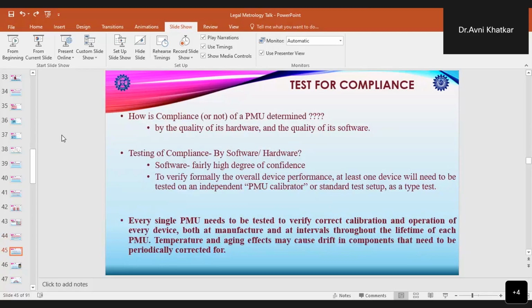Now when we talk about the test for compliance, whether the PMU is compliant or not will be determined by the quality of its hardware and the quality of its software. The PMU software can largely be designed by using mathematical tools, and it can be tested in simulation in conjunction with the knowledge of the PMU hardware constraints, giving a higher degree of confidence that the PMU will behave appropriately. These activities can be carried out at the manufacturer premises. However, in order to verify formally that the overall device performance, at least of a single device, is appropriate, these activities should be carried out in a formal environment at an independent PMU calibrator or a standard test setup as a type test.